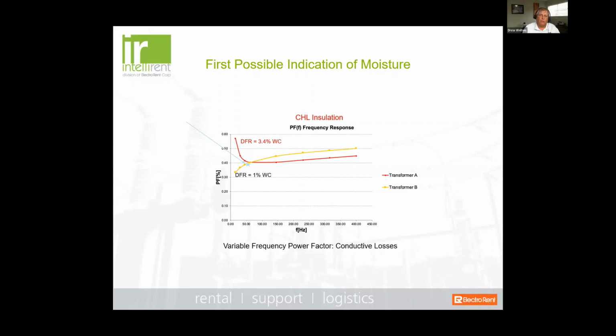Now, what's a conductive loss? Well, that could be furans, it could be sludge, excessive sludge in the oil. Could be a number of things, but one of the things it could be is moisture. All right, so if we have two like transformers that we've done a 60 hertz measurement at, and they both look identical, but when we look at the lower frequency, say from 10 to 60 hertz, we check if it's coming in higher or coming in lower. If it's coming in lower, that means we probably don't have any conductive losses to be concerned about. Now, if that coincides with your ppm measurement, you should be good to go.